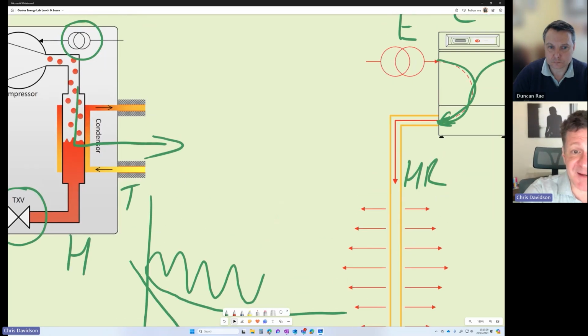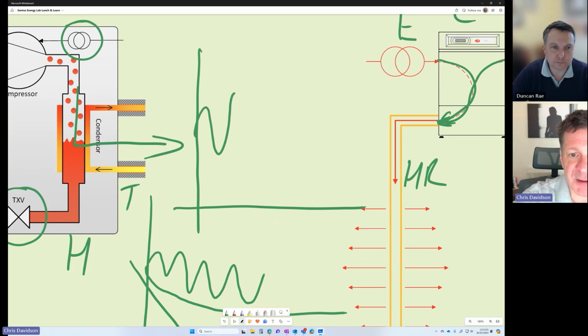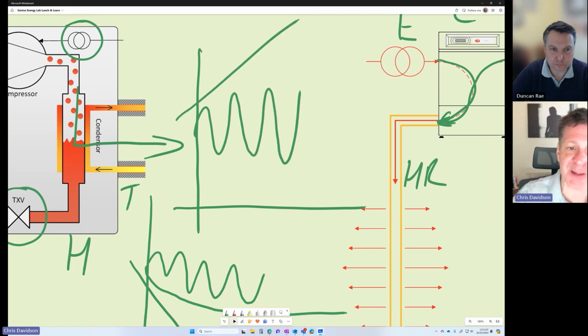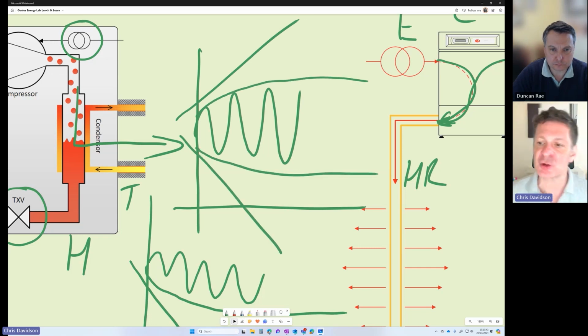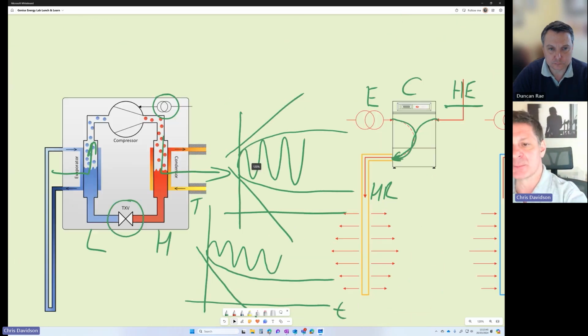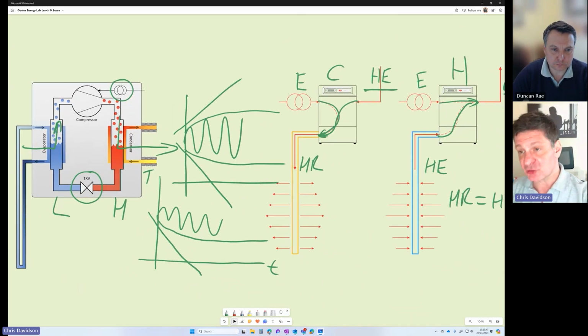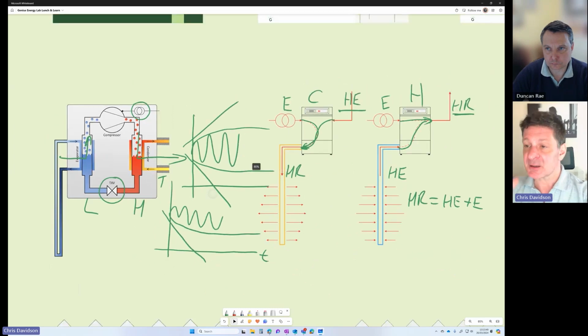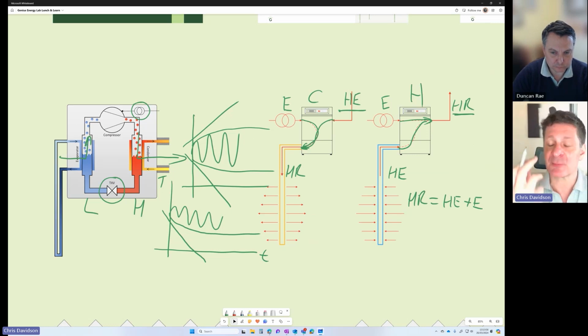If we look now at a heating and cooling system, that graph goes in both directions - warmer in summer, colder in winter. Again we don't want it galloping hotter and hotter or colder and colder. We want it to tend to a limit, inside the efficient operational window of that heat pump. So that, in a nutshell, is ground source design: given what we need to do in the building, and the properties of that heat pump, how much pipe do we need to put in the ground to make it sustainable in the long term?